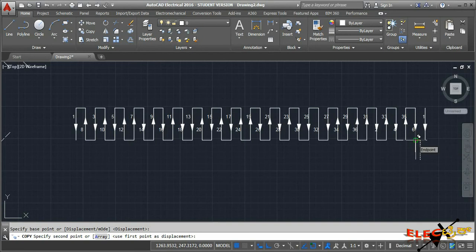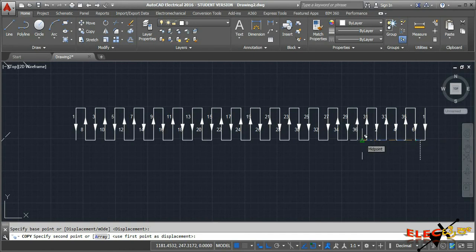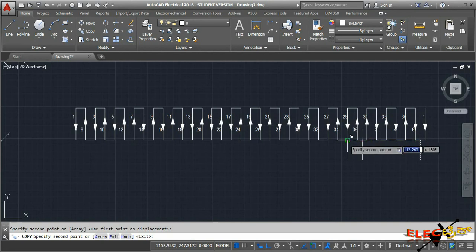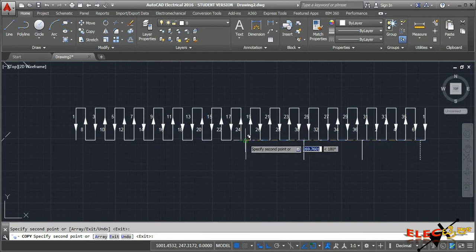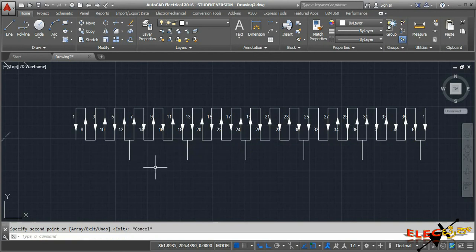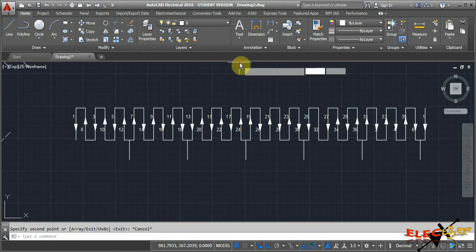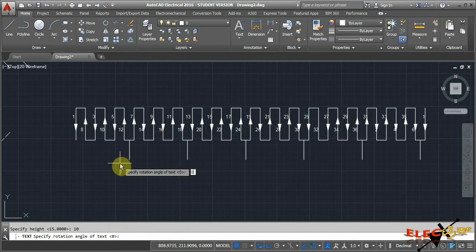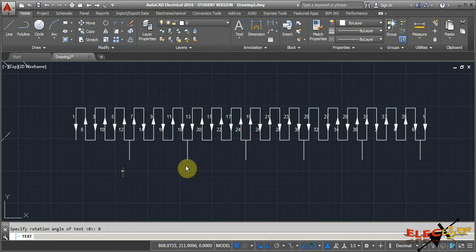The brush position is where adjacent conductors have the same current direction. Conductors 1 and 6 have the same direction, conductors 36 and 31 have the same direction - draw a line there. Similarly at conductors 30 and 25, 24 and 19, 18 and 13, and 12 and 7. For upward direction conductors indicate negative polarity; for downward direction indicate positive polarity.